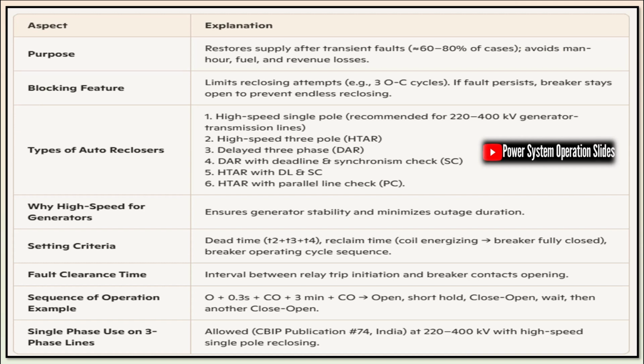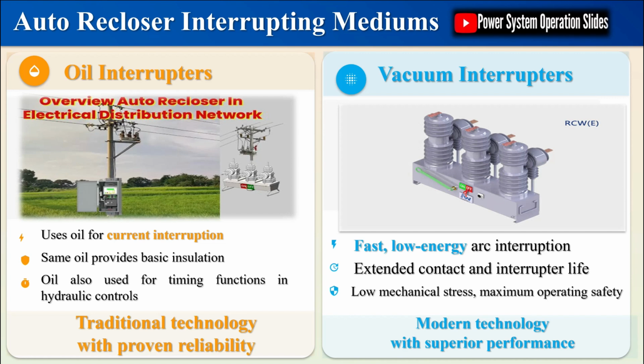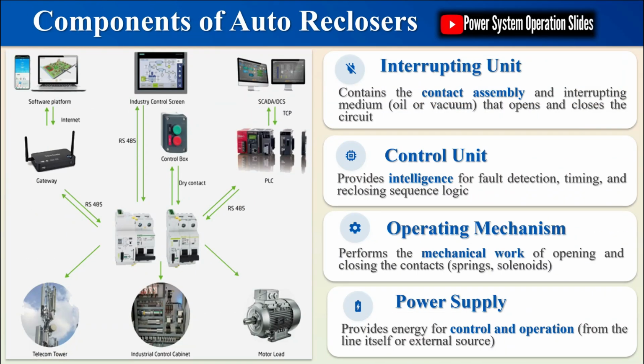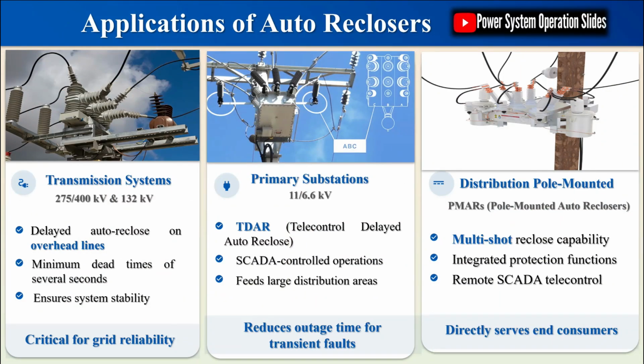3. Triple single reclosers. These are electronically controlled and have three modes of operation. Three-phase trip and three-phase lockout. All three phases simultaneously trip on an overcurrent, reclose, and sequence together. Single-phase trip and three-phase lockout. Each phase operates independently for overcurrent tripping and reclosing. If any phase sequences to lockout condition, due to permanent fault, or if lockout is locally or remotely asserted, the other two phases trip open and lock out.